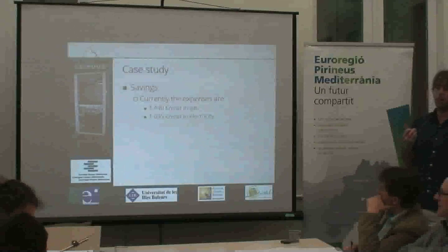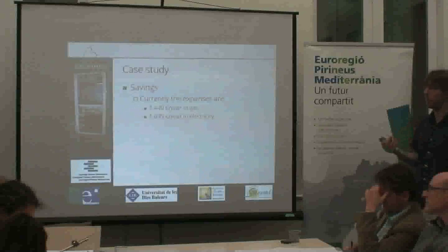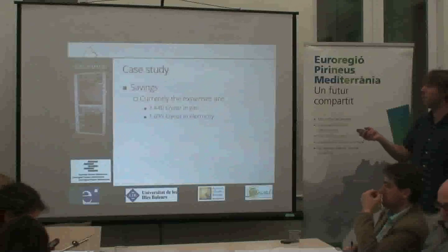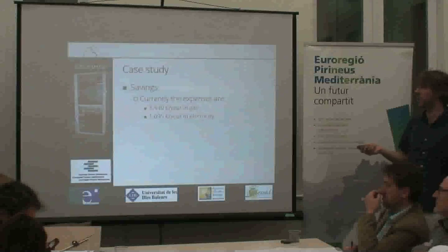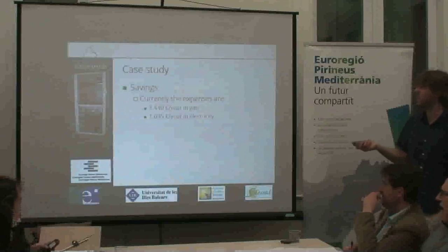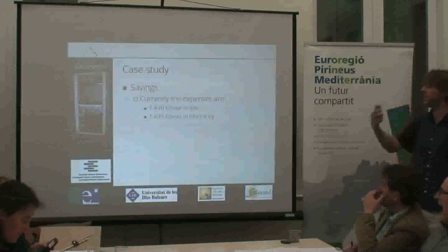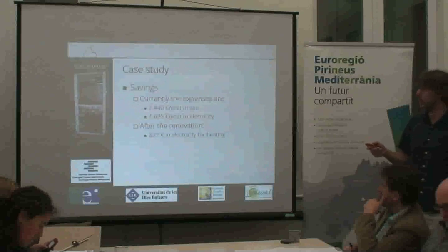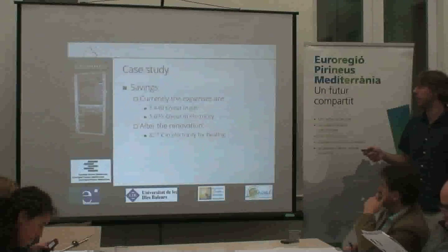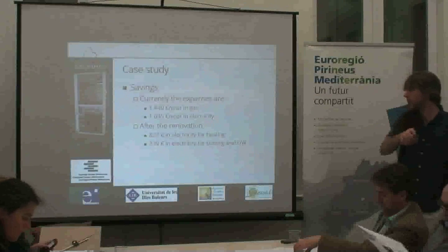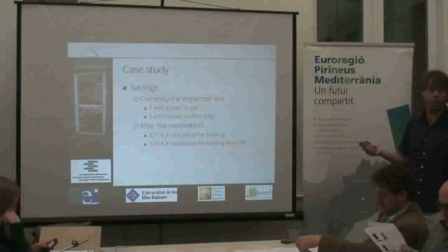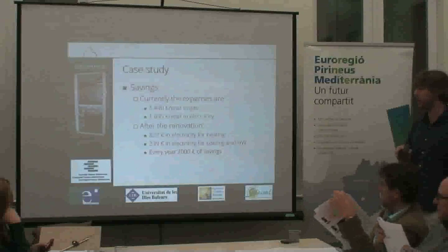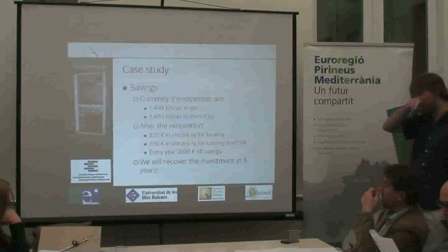Which will be the savings. Okay, now we're talking in euros, in money. It's what people are expecting from this technology. Those people, with the current tariff, were spending 1,500 euros per year in gas and 1,700 euros per year in electricity. What will happen after the installation is done, after the renovation? They will just pay 800 euros in electricity for heating, and 300 euros in electricity for cooling and hot water. So in total, they will have more or less 2,000 euros per year of savings. More or less, this investment will be recovered in 5 years.